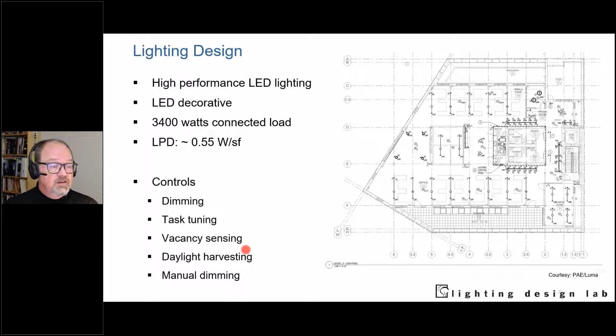The controls were value engineered, essentially cheapened to save a couple thousand dollars. They were supposed to meet energy code, and technically we got a certificate of occupancy, but it was impossible to control the lighting. We're a high performance MEP and lighting design firm, and in one of the best daylighted buildings around, it wasn't possible to turn the lights off. Every time we tried, some bizarre emergency system would turn these lights back on along with corresponding ones on the other side. It was literally not possible to turn the lights off.